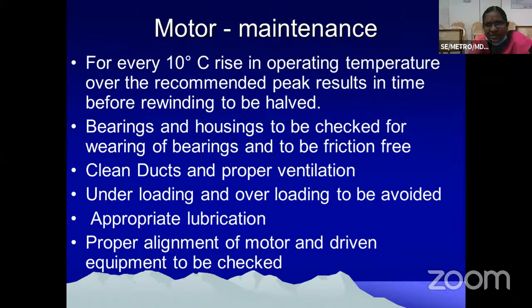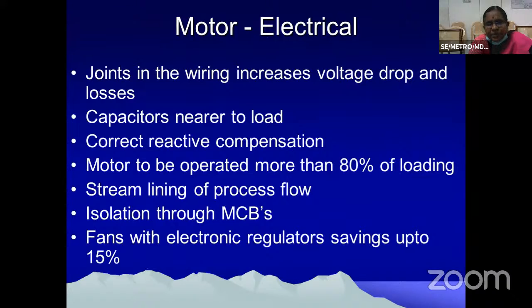Bearings and housings to be checked for wearing of bearings and to be friction free. Clean ducts and proper ventilation. Underloading and overloading to be avoided. Appropriate lubrication has to be done. Proper alignment of motor and driven equipment to be checked. Joints in the wiring increases voltage drop and also losses.